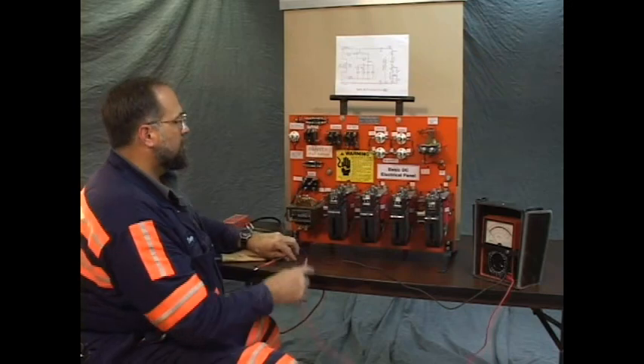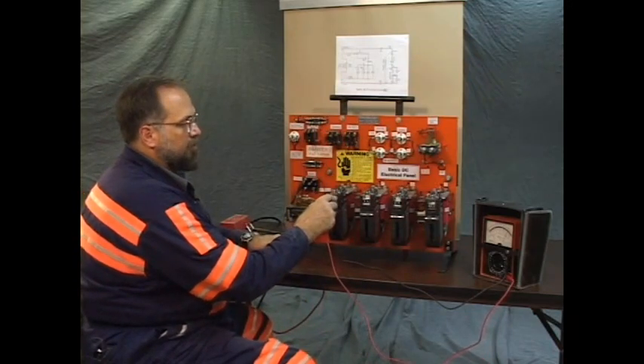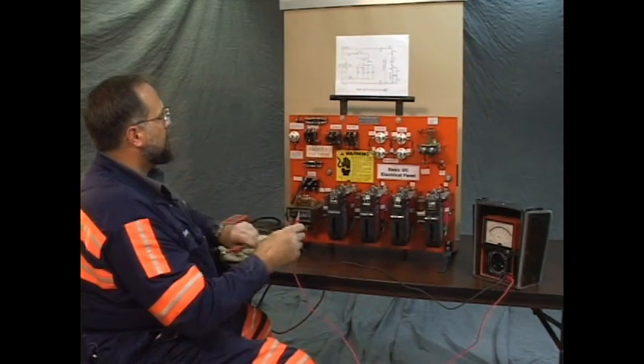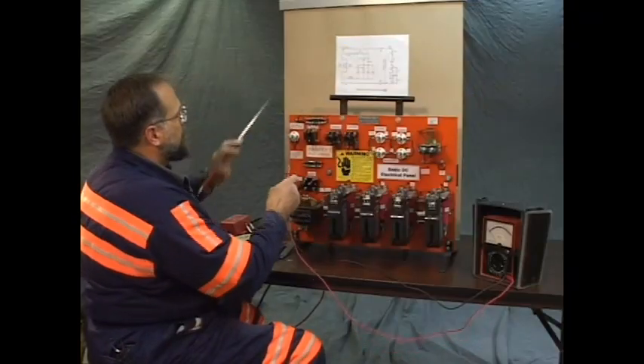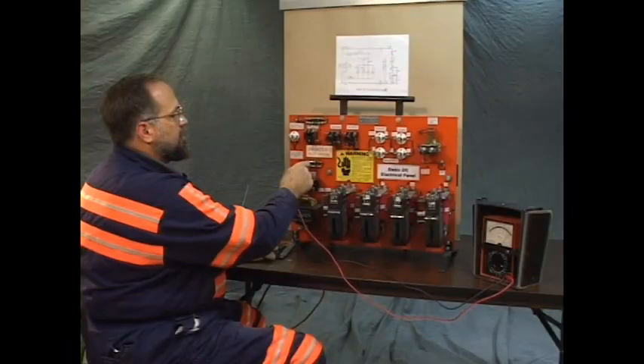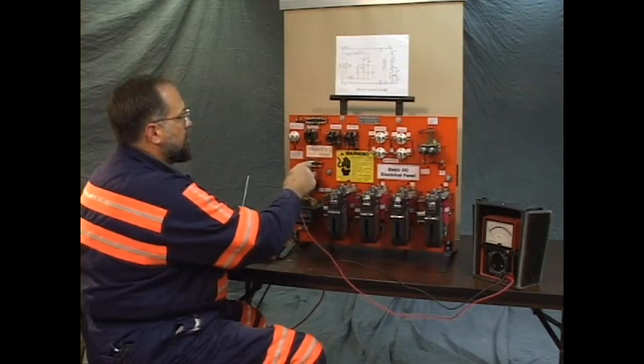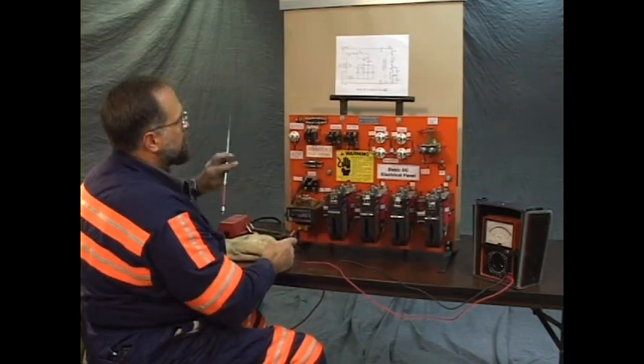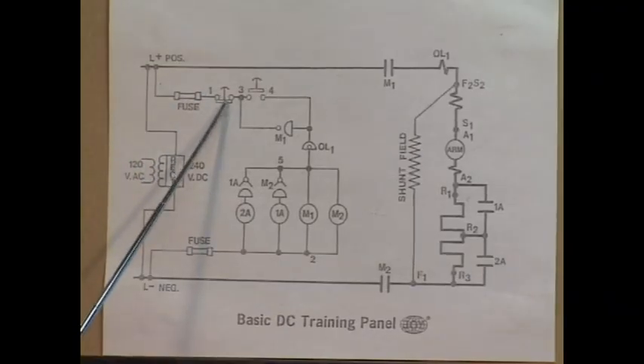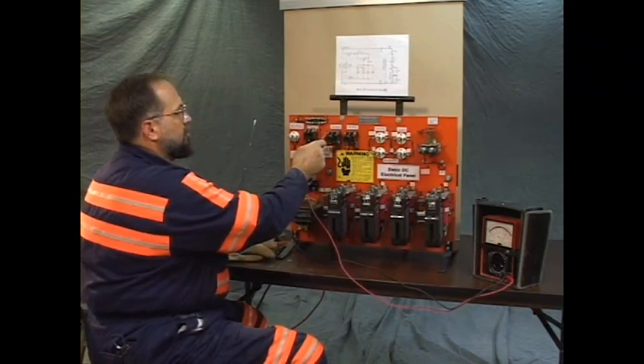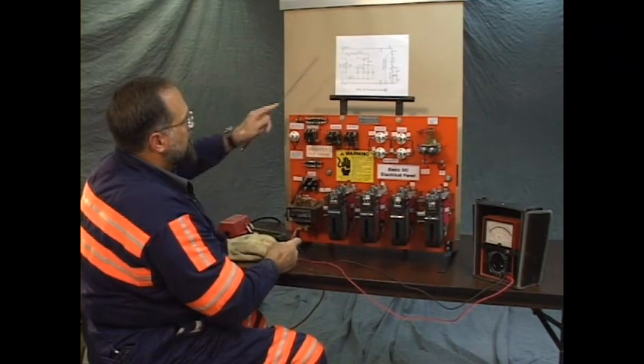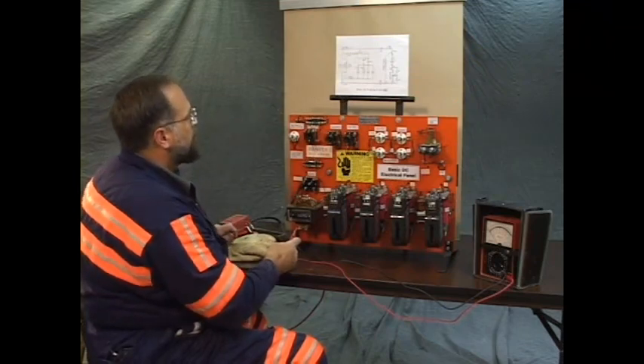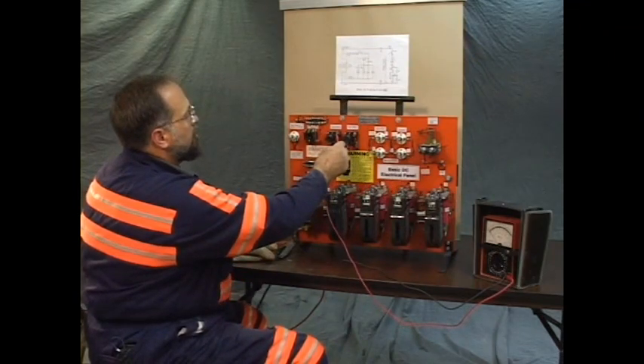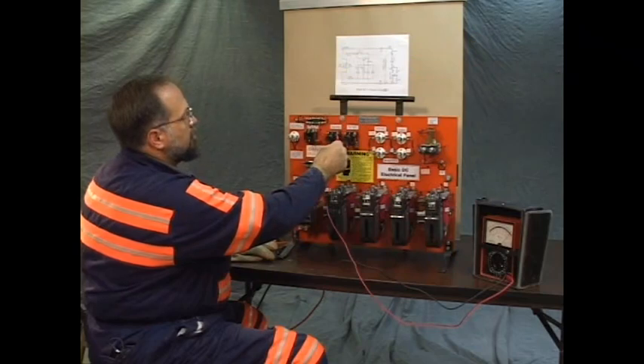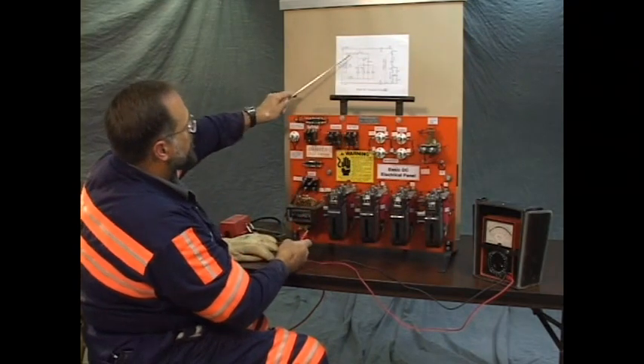Now, to resume, our first test was top front of M1, and it was good. The next point that we test, the line side of the positive fuse, and it's good. Let's test through the fuse. If the fuse has continuity, we'll read it here, and it is good. The next point, line side of the stop switch, and it's good. The stop switch is normally closed. It's a momentary push button. So we're going to read to load side of the stop switch, and it's good. That's reading across.